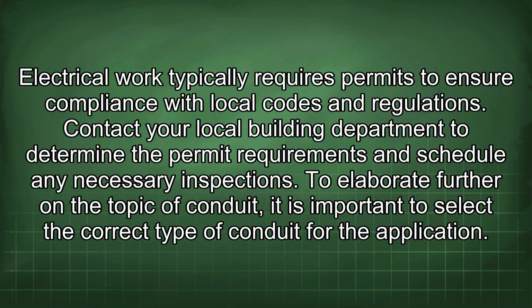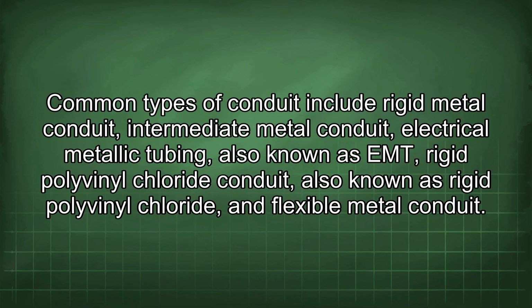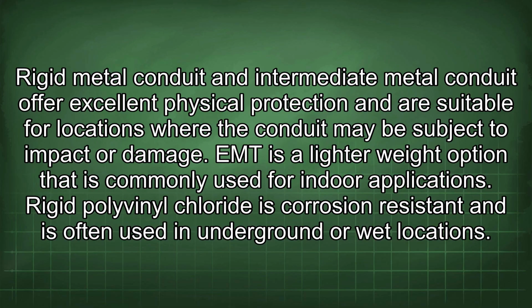To elaborate further on the topic of conduit, it is important to select the correct type of conduit for the application. Common types of conduit include rigid metal conduit, intermediate metal conduit, electrical metallic tubing, also known as EMT, rigid polyvinyl chloride conduit, and flexible metal conduit. Rigid metal conduit and intermediate metal conduit offer excellent physical protection and are suitable for locations where the conduit may be subject to impact or damage.